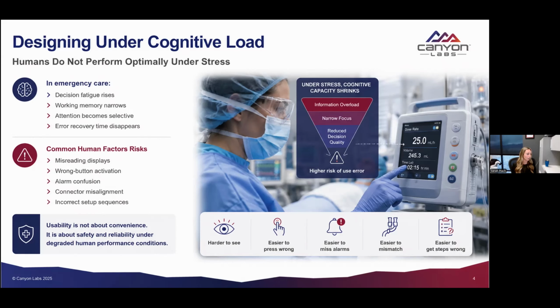Connector misalignment is another one we see, along with incorrect setup sequences. Again, you're doing things fast, and if it's not intuitive, we see people miss it. Typically, what we recommend in the design inputs we're giving to individuals designing a device for this space is colors and symbols, and you can even make sure that they don't connect at all. There's two devices we work on in the suction space. If you misconnect a piece of it, it alarms, and there's a piece that you'd really have to shove in there, and it would not connect if you were forcing it.